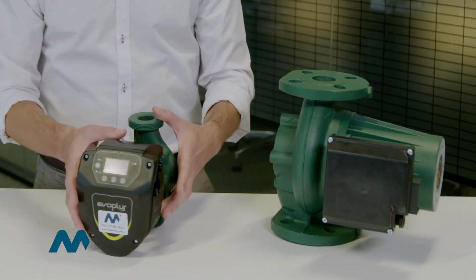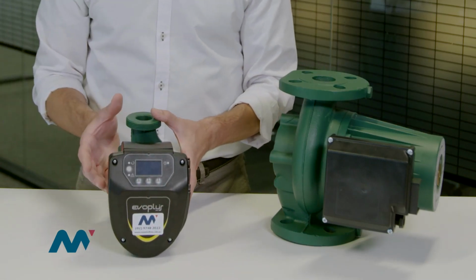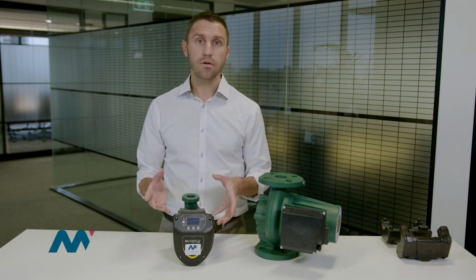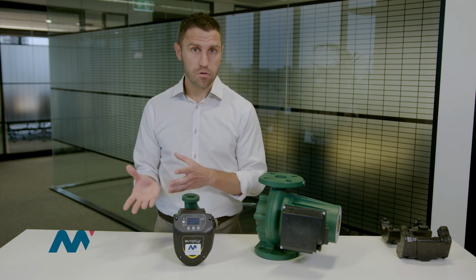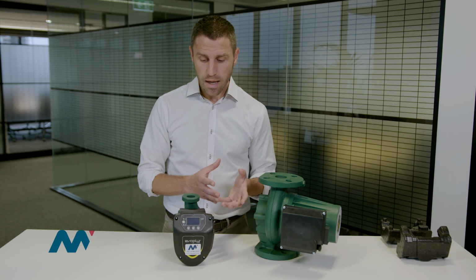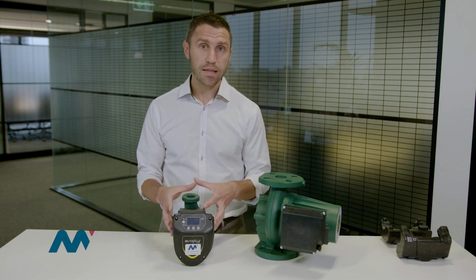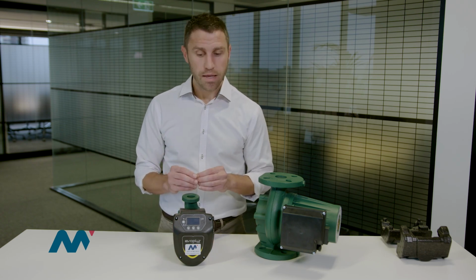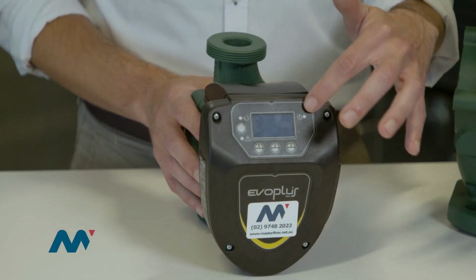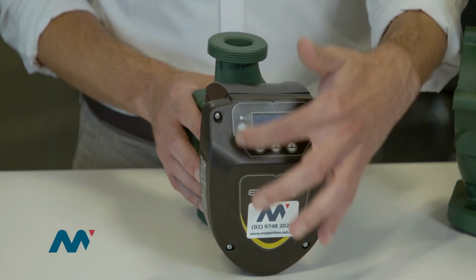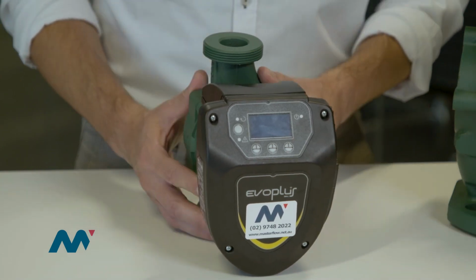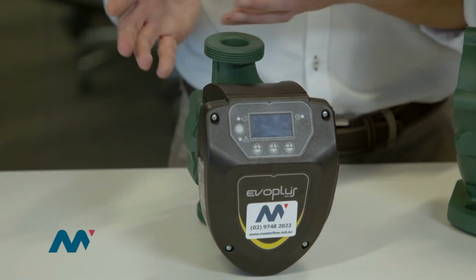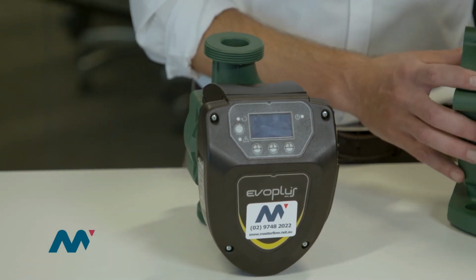While with this pump, if you open the covering here, you can find different terminals for multi-inverter, for serial communication, for remote on-off, for temperature sensor, and also for connectivity, to have the data of your pump online, for example, and you can have remote monitoring. Another big advantage is the display, so you can actually visualize what the pump is doing and see the performance that it is currently delivering. So these are mainly the advantages of a variable speed pump compared to a 3-speed circulator.